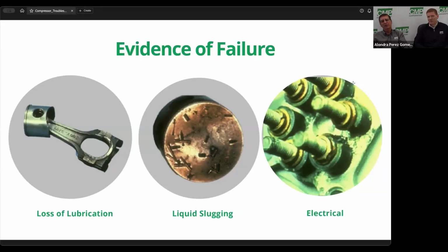I'll tell you also, though, when you come up on a compressor and it's all burnt, it really doesn't mean that you have an electrical problem. You still could have a mechanical problem. What we haven't touched on is if you have a slug and your suction reeds are busted all to pieces and your piston looks like sandpaper, like it's been bead blasted, then change the compressor. All those little pieces on the suction reed, not the discharge, because it goes right out the discharge, but on your suction reed, if they get in and get on top of the electric motor, it might be a day, it might be a week, it might be a month, but sooner or later, it's going to burn the compressor up. So every time you have a burnt compressor, just don't think, okay, I have an electrical problem. You may have a mechanical problem also, and that's what caused the compressor to burn.